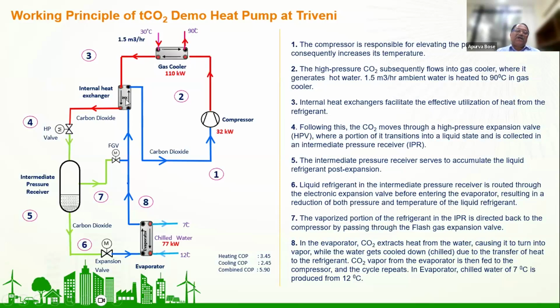Post which it passes through the internal heat exchanger, where obviously the pressure remains the same. However, the temperature comes down a little bit, and then we pass it through a high pressure valve expander, and from here it goes to what we call the intermediate pressure receiver, or IP receiver. Here the CO2 comes in two phases, liquid as well as gaseous. The gaseous part we again pass through a flash gas valve, and we put it back to the IHX, from where it goes back to the compressor again.